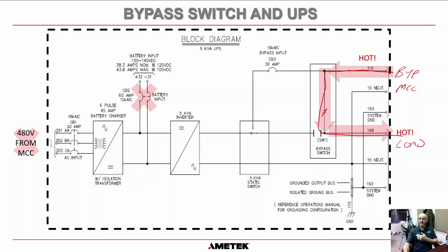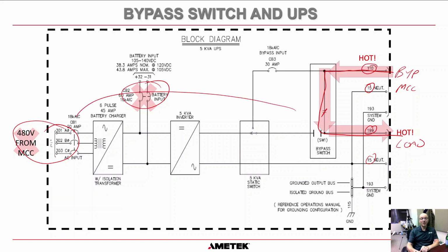So within an AMETEK Solid-State Controls UPS, wire 110 and 15 are still going to remain live or hot, and wires 199 and 15 are still going to be live or hot. Okay, yes, you can disconnect the battery. Yes, you can disconnect the 480 volts at the upstream MCC, but you cannot go and work in the inverter, battery charger, or static switch safely, because you still have power here at the terminals inside the UPS itself. So you can't deem this cabinet to be volt free to go and do work.